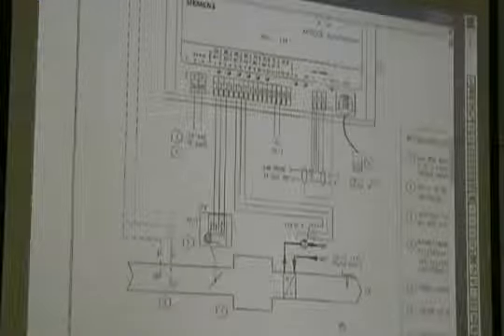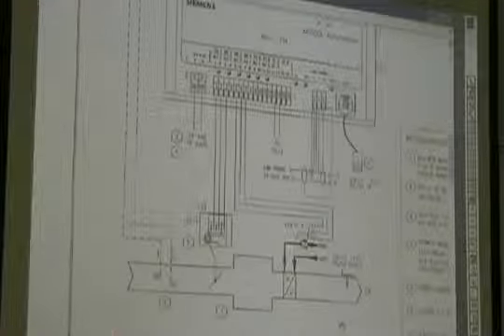Now, looking at this diagram down here, this is a representation of our VAV box. We have air coming from the air handler entering this side. We've got some kind of airflow pickup. Most of the time it's what we call either a flow cross or cross flow. Those are specific terms for different manufacturers. So that's some kind of airflow pickup. Right here is our variable volume damper, and we're showing we've got a damper actuator tied to that damper.